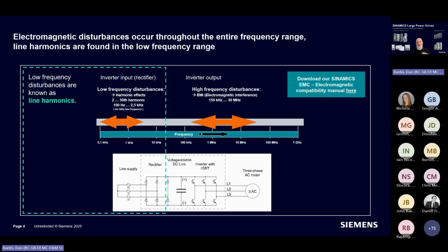The harmonics we're talking about today, line harmonics, are low frequency disturbances, but tend to be high power relative to the load. We're normally looking at up to the 50th, or even in the UK these days typically the 100th harmonic - that's from 2 times the base frequency, so 50 hertz in the UK, up to 100 times, or up to 5 kilohertz. That is typically high power relative to the load you're consuming.